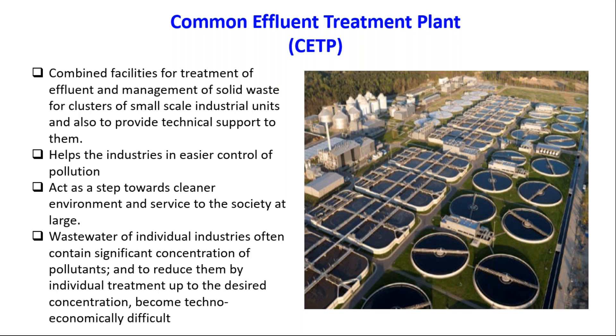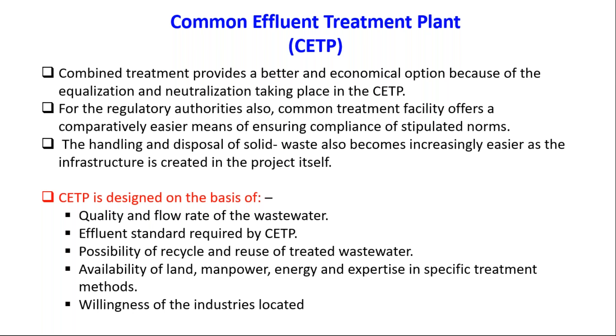CETP requires permission from the State Pollution Control Board (SPCB) and the Central Pollution Control Board (CPCB). The SPCB observes the site layout, the facilities to be created at the CETP, and monitors all the activities treating effluent. Combined treatment provides a better and economical option because of the equalization and neutralization techniques used in CETP. For regulatory authorities, the common treatment facility offers a comparatively easier means of ensuring compliance with stipulated norms.